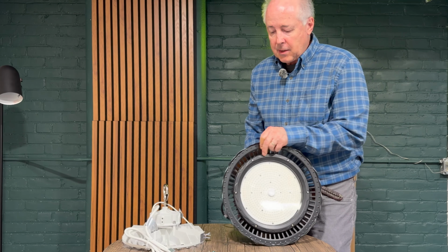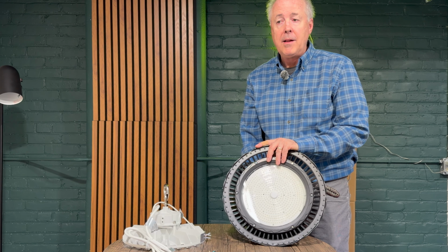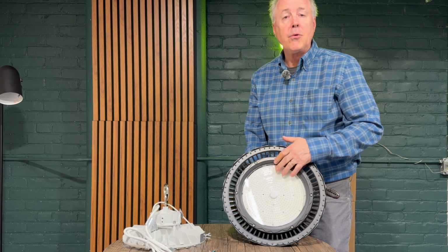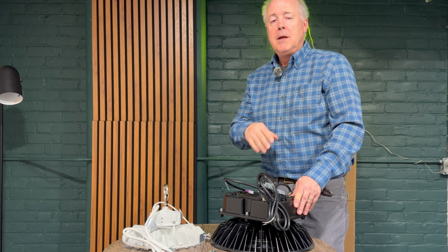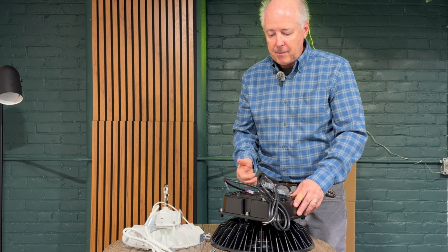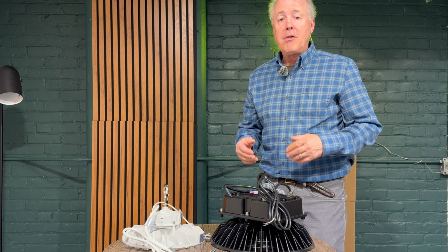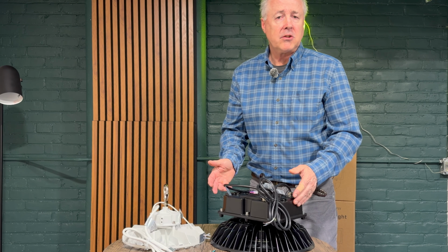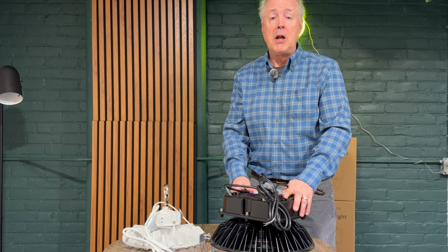It also comes in a lot of different wattages. This one's a 300 watt, but we go all the way up to 500 watt. There's a tempered glass lens. You can hit this with a hammer. As you can see, it's much more rugged, with a bigger heat sink, and can handle those environments. You also can get a pendant mount, and it comes in high voltage, with a lot of different options. Usually in an industrial environment, motion sensors aren't required, but we do have versions that provide motion sensor functionality if you want that.